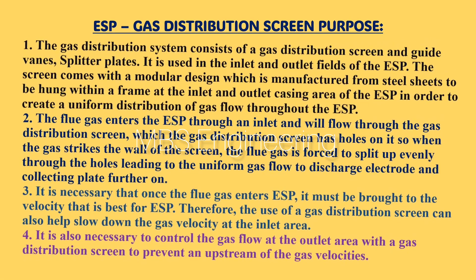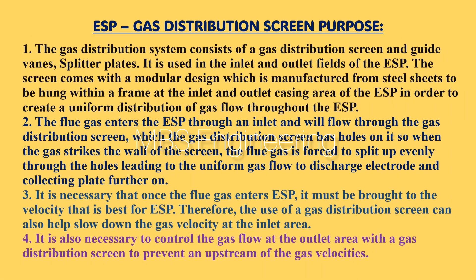Point 2: the flue gas enters the ESP through an inlet and flows through the gas distribution screen, which has holes on it. When the gas strikes the wall of the screen, the flue gas is forced to split up evenly through the holes, leading to uniform gas flow to the discharge electrode and collecting plate.